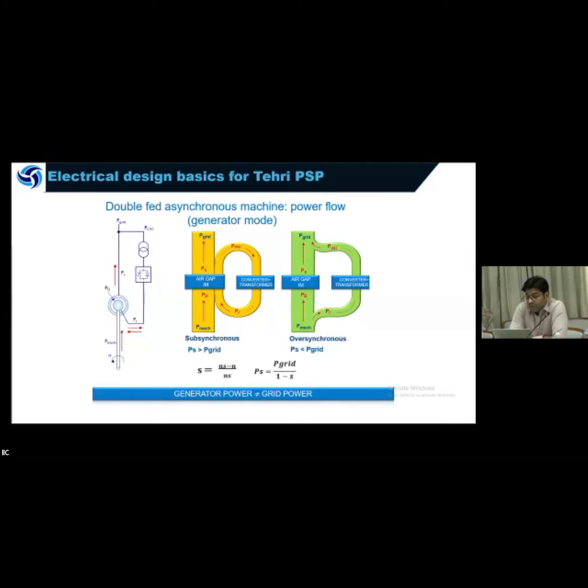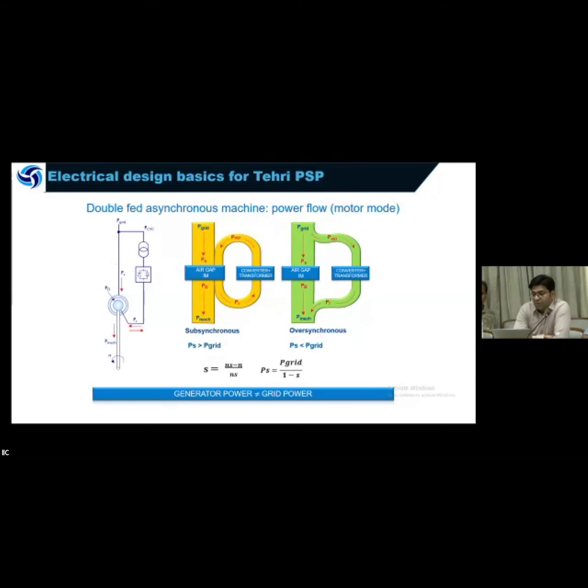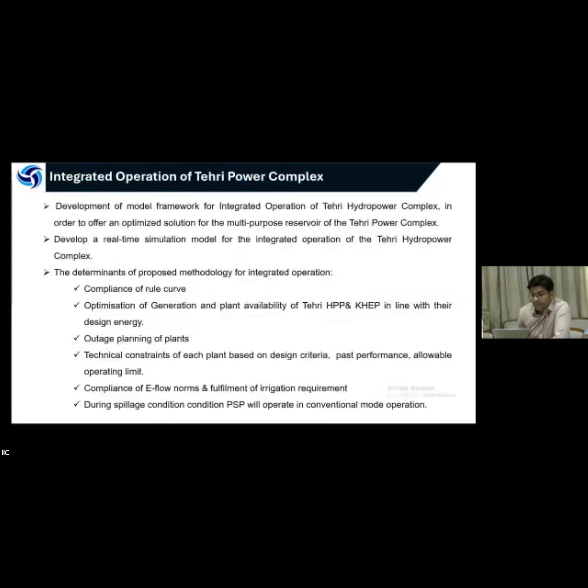If it operates at the supersynchronous speed, then the mechanical power will be divided into two parts. The first part is the stator power, and the second one is the rotor power. Both the rotor and stator will feed the power to the grid. Similarly, in motor mode, in subsynchronous, the mechanical power, the stator power will be the grid power, and for the supersynchronous mode, the power is further divided into the stator power and rotor power.